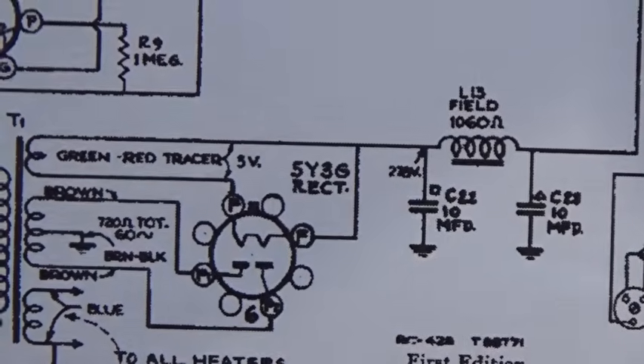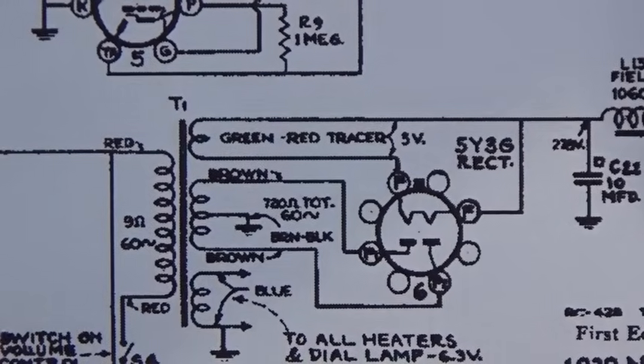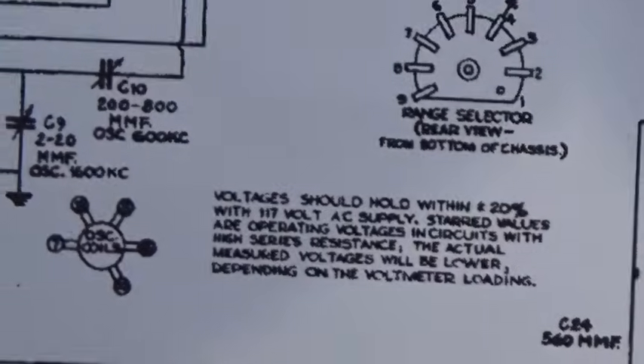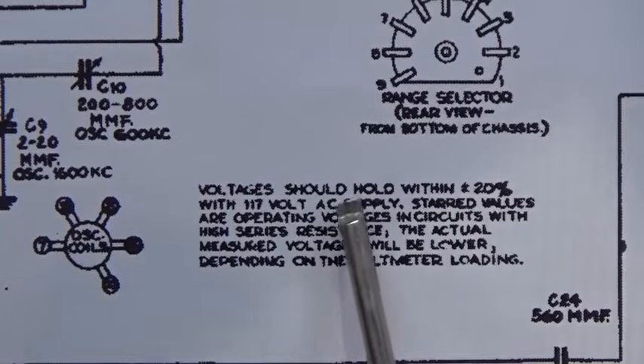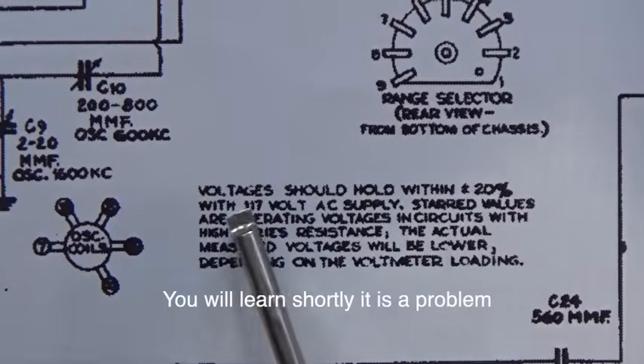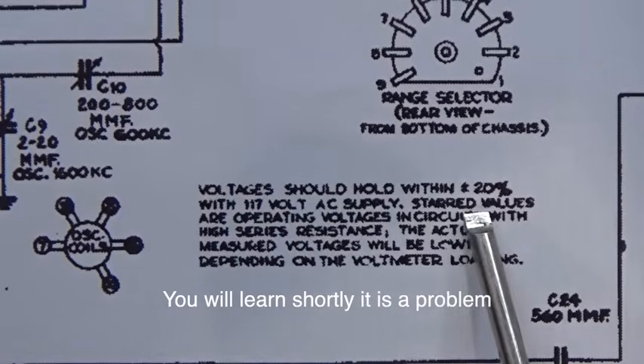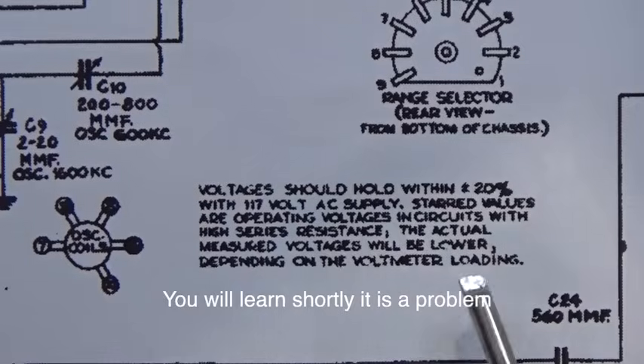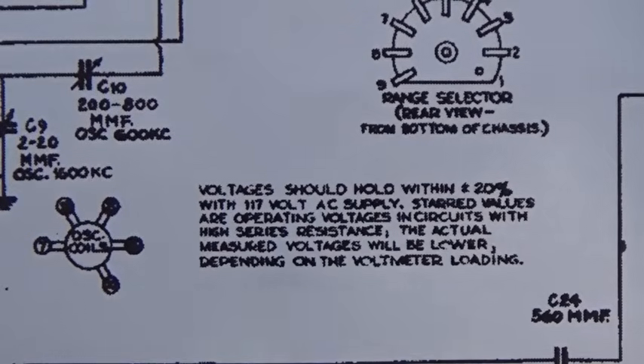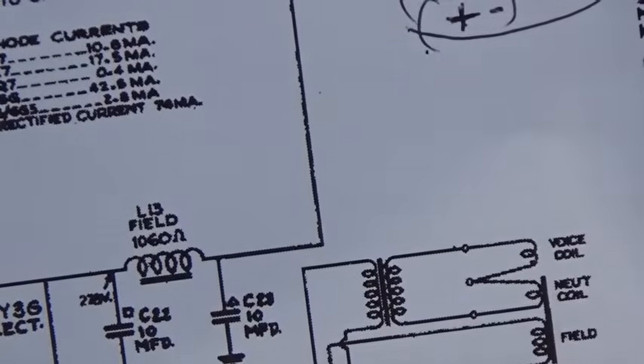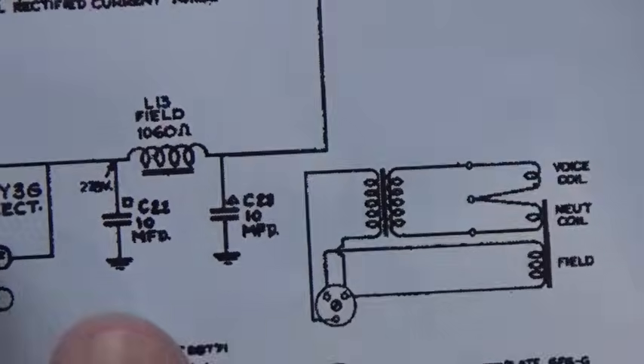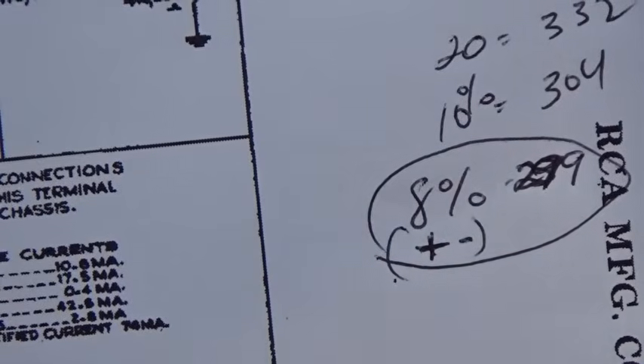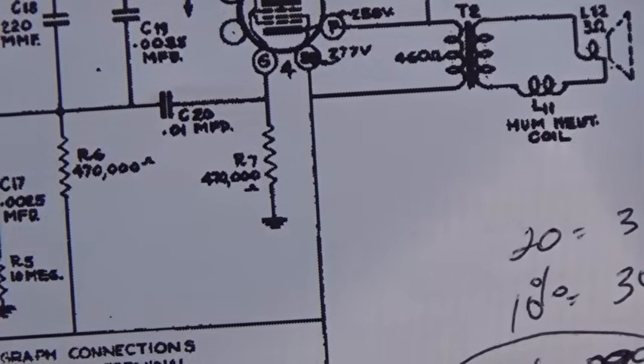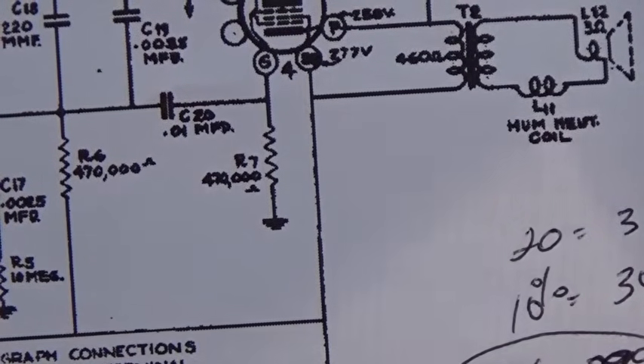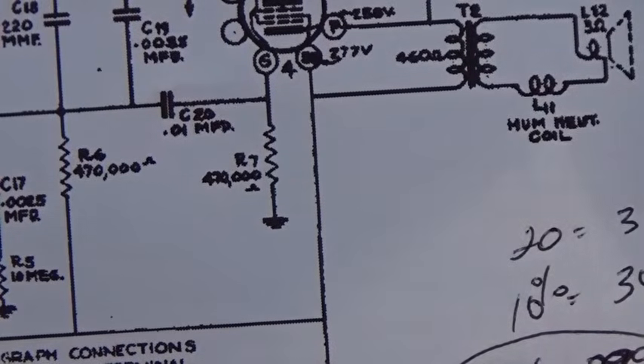Well, we're getting 300. Is that a problem? Not really, and I'll tell you why. If you look at the fine print, it says voltages should be held within 20% with a 117 volt AC power supply. So if you take the 277 volts and the 300 volts we're getting on the meter, it equates to about 8%. I did the math just to prove it out. So we have an 8% differential in the radio, and that's because the line voltage is no longer 117, it's a little higher.